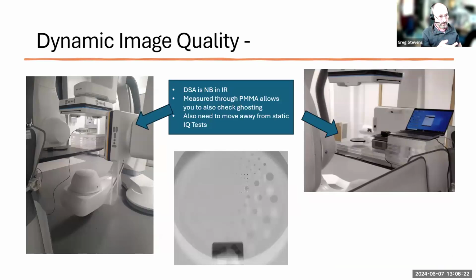Because of the recursive filter, we started playing around with some dynamic image quality. We've got a Motus phantom. We've also got a DSA test object, which works very well. The one we've got is a Leeds one, I believe. The Motus, however, is quite interesting. This image is a TO10 with the actual movement on at the time, and you can see there is an awful lot of ghosting. I'm assuming this is down to the recursive filter, because it wasn't moving so fast that it should have been an issue.